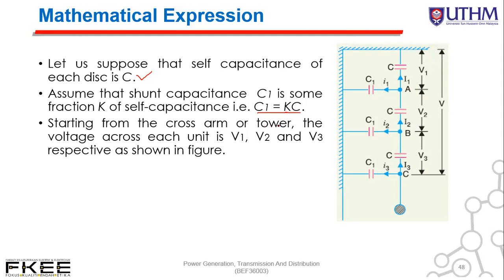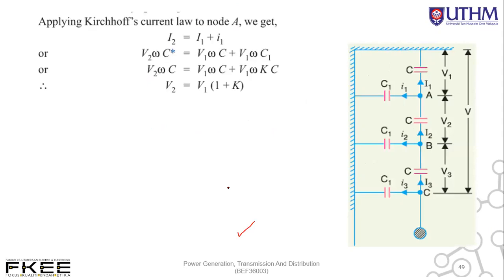Starting from the cross arm or tower, the voltage across each unit is V1, V2, and V3. Applying KCL at node A: I2 = I1 + i1 (current into C1), giving V2·ωC = V1·ωC + V1·ωC1. Since C1 = KC, we simplify to get the first equation: V2 = V1(1 + K).